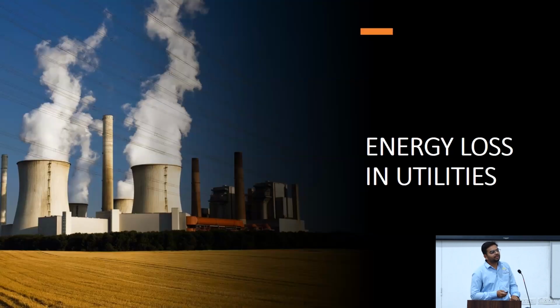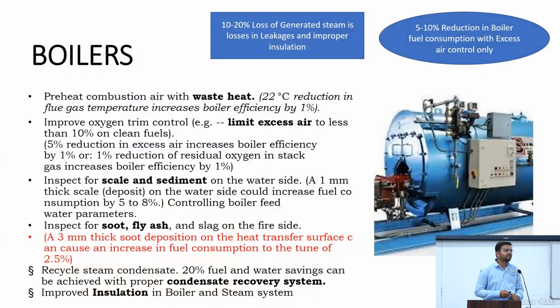So there are normal energy savings in utilities also. These were the specific cases for specific industries. Now, what are the normal practices we follow for energy savings? In the boiler, we can preheat our combustion air. This is normal practice now; every boiler is supplied with an APH. But if the boiler is not supplied with an APH, every 22 degree reduction in the flue gas temperature can increase boiler efficiency by 1%. It is a direct relation.